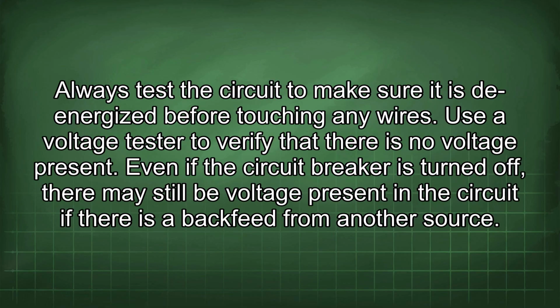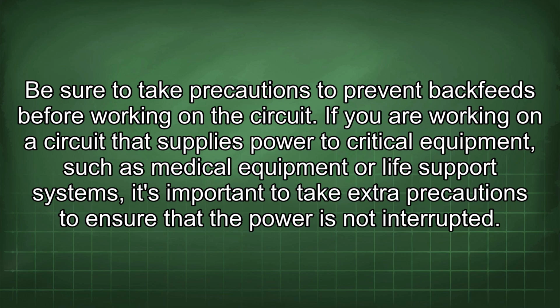Always test the circuit to make sure it is de-energized before touching any wires. Use a voltage tester to verify that there is no voltage present. Even if the circuit breaker is turned off, there may still be voltage present in the circuit if there is a backfeed from another source. Be sure to take precautions to prevent backfeeds before working on the circuit.